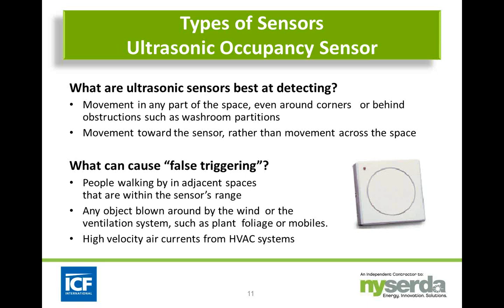What can cause false triggering with ultrasonic? People walking by in adjacent spaces that are within the sensor's range, so you have to make sure you've commissioned it properly to read the space that you're working with as opposed to outside the space. If there's an object that gets blown around in the space, then you might actually have some false triggering there. I had an instance years ago where there was a heat duct right outside the door of a lawyer's office, and when somebody would walk by, it would push the heat into the space and it would move the paper on the desk, and that would actually falsely trigger the unit. So you have to be careful about those kind of applications.